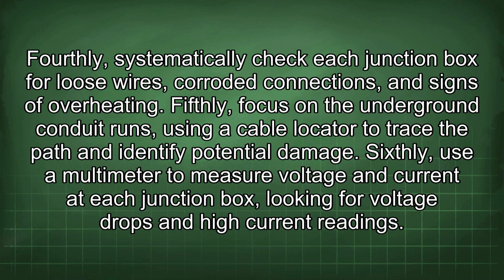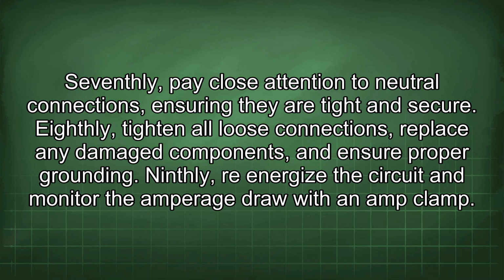Sixthly, use a multimeter to measure voltage and current at each junction box, looking for voltage drops and high current readings. Seventhly, pay close attention to neutral connections, ensuring they are tight and secure. Eighthly, tighten all loose connections, replace any damaged components, and ensure proper grounding. Ninthly, re-energize the circuit and monitor the amperage draw with an amp clamp.